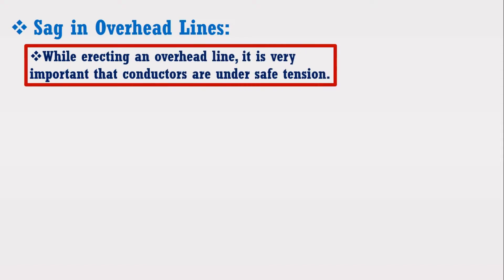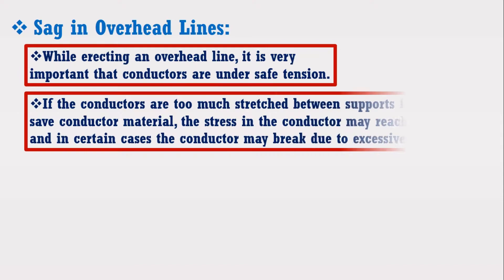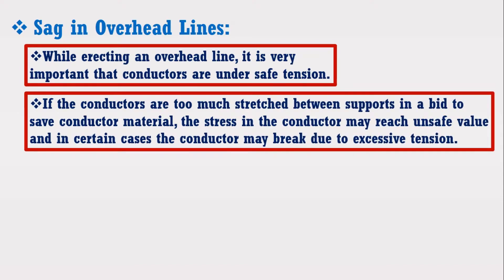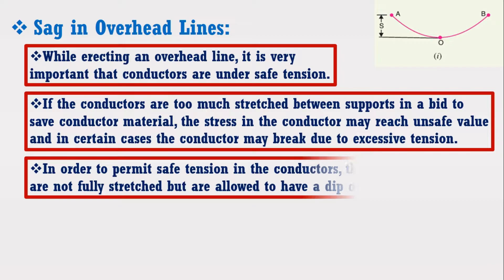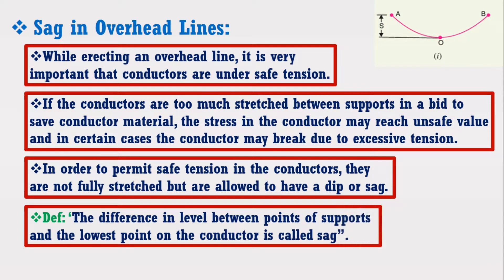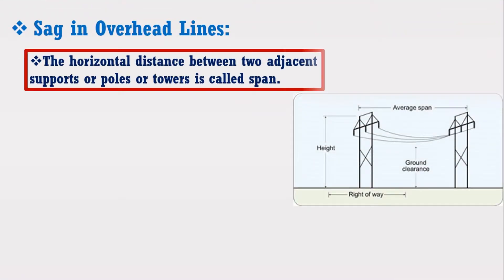While erecting an overhead line, it is very important that conductors are under safe tension. If the conductors are too much stretched between the supports in a bid to save the conductor material, the stress in the conductor may reach unsafe value and in certain cases the conductor may break due to excessive tension. In order to permit safe tension in the conductors, they are not fully stretched but are allowed to have a dip or sag. The difference in level between points of supports and the lowest point on the conductor is called sag. Furthermore, the horizontal distance between the two adjacent supports or poles or towers is called span, as shown in the figure.